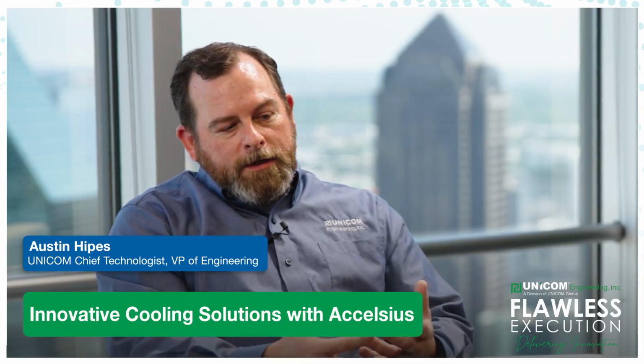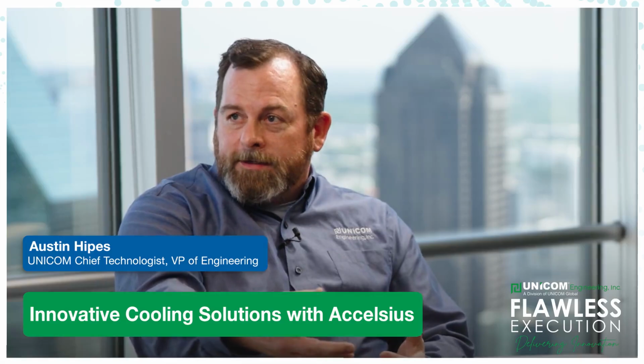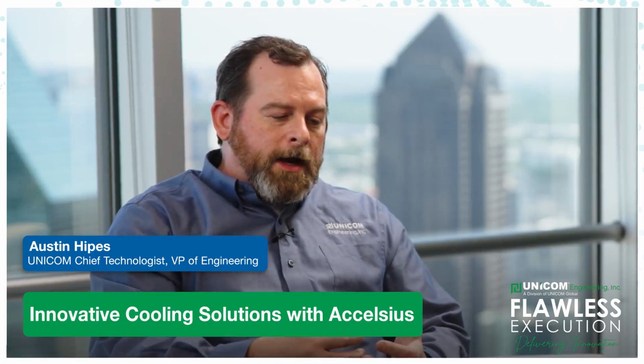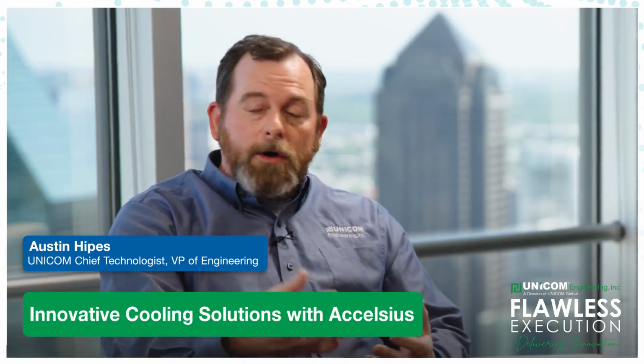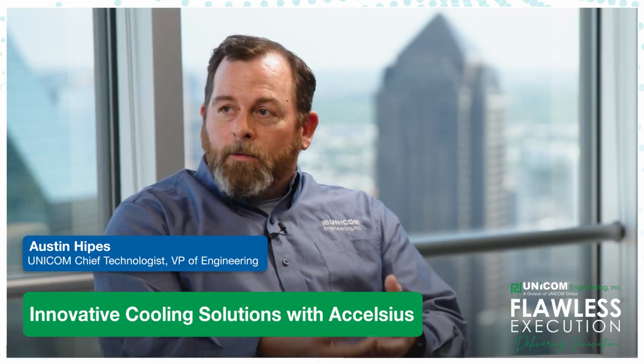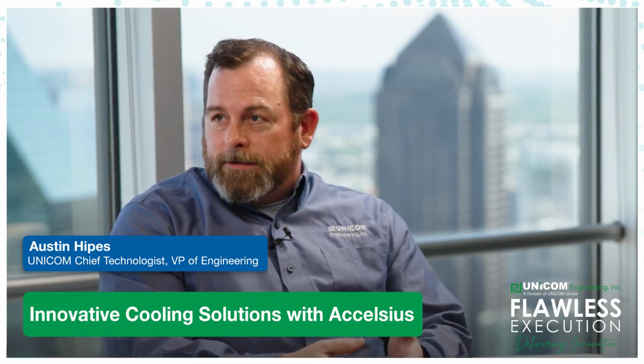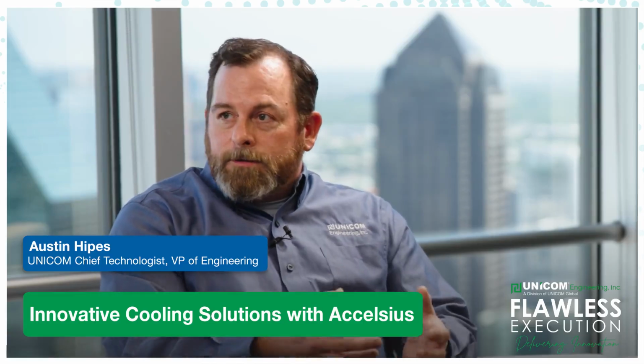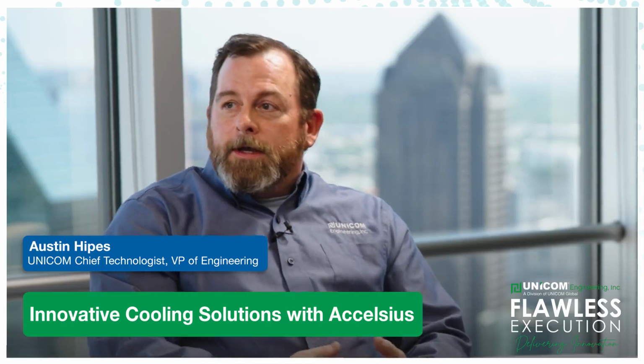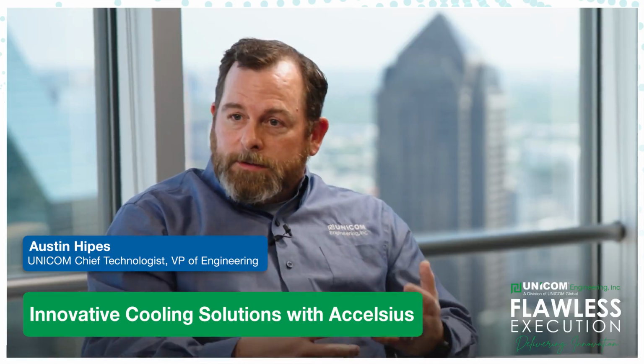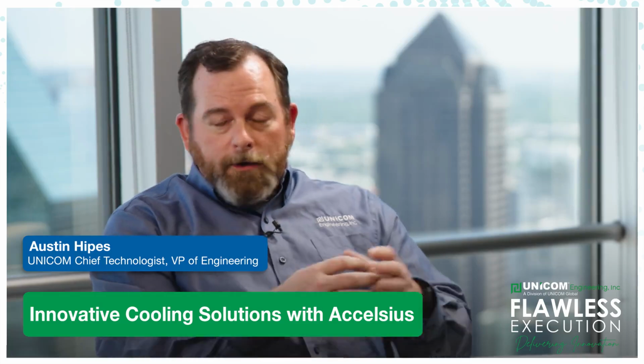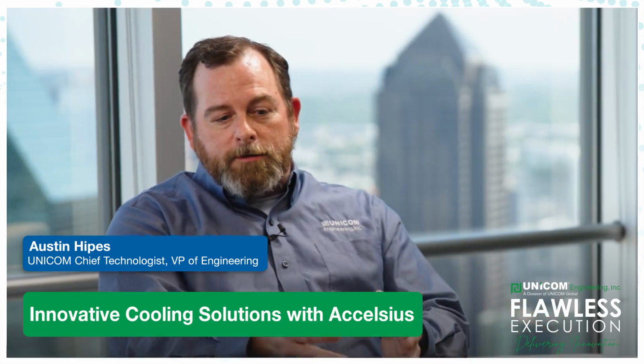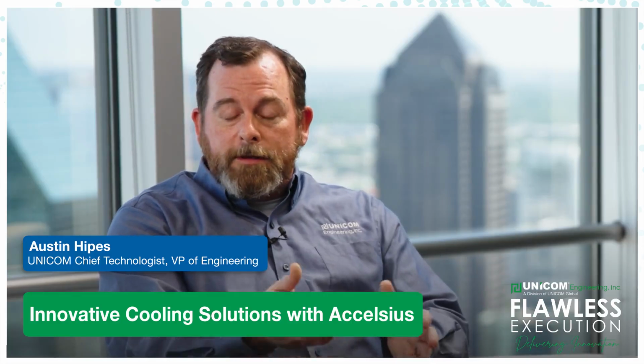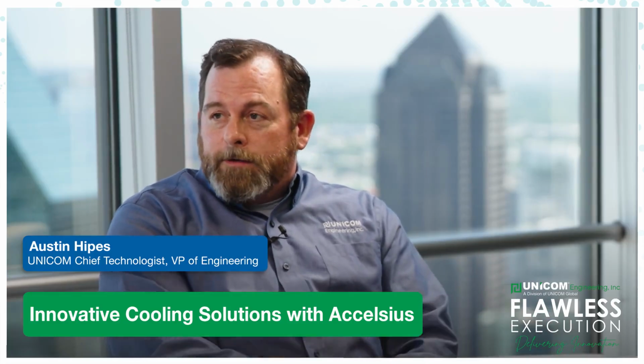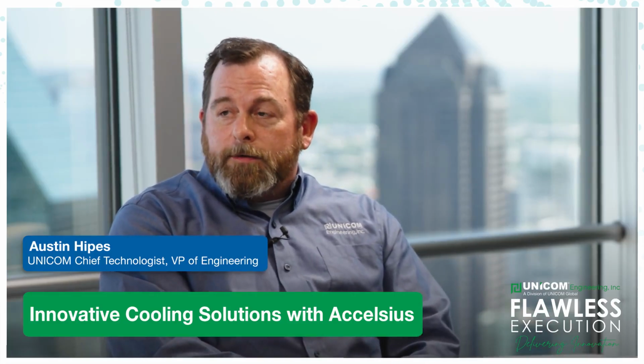And what that really means is that on the heat rejection side of the data center, you can use higher water temperatures in your water cooling loop. By using higher water temperatures, it allows it to be more energy efficient. You don't have to run compressors, you can do things like dry coolers, and those dry coolers are a closed loop system with no wastewater. So not only is it more energy efficient, but it also allows many data centers to use little to no wastewater, which is important in a lot of regions of the world.